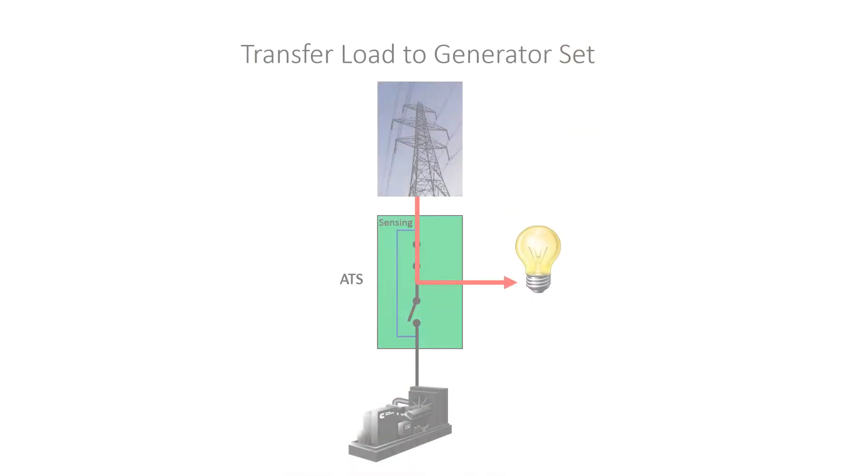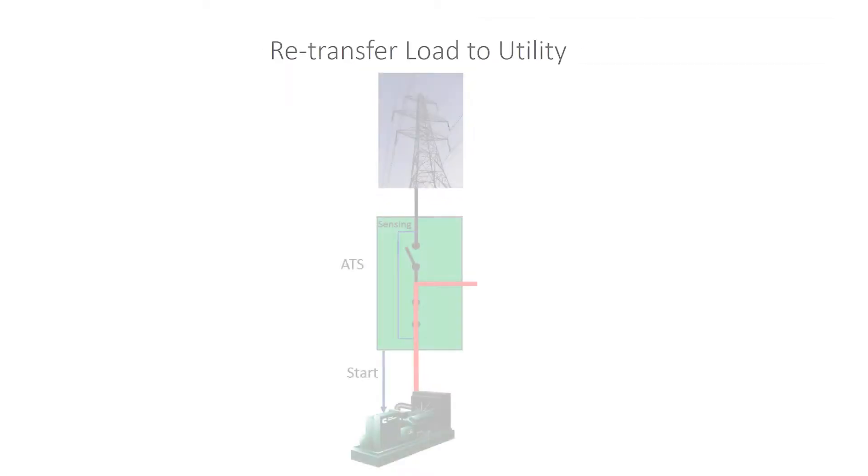When the ATS control senses that the voltage and or frequency of the utility are not within the acceptable limits, it sends a start signal to the generator. When the generator set is ready to accept load, the ATS transfers the load to the generator. Once the utility source returns and becomes stable again, the ATS automatically transfers the load back to the utility and removes the start signal from the generator to allow it to shut down.